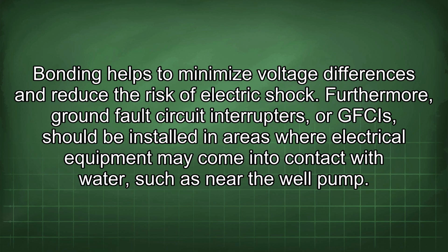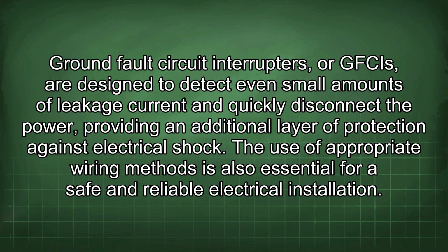Furthermore, ground fault circuit interrupters, or GFCIs, should be installed in areas where electrical equipment may come into contact with water, such as near the well pump. GFCIs are designed to detect even small amounts of leakage current and quickly disconnect the power, providing an additional layer of protection against electrical shock. The use of appropriate wiring methods is also essential for a safe and reliable electrical installation.